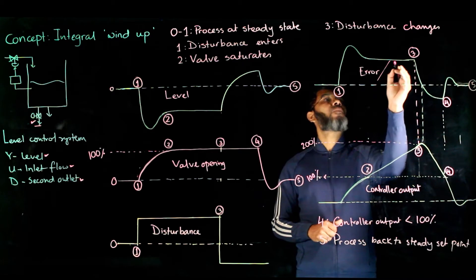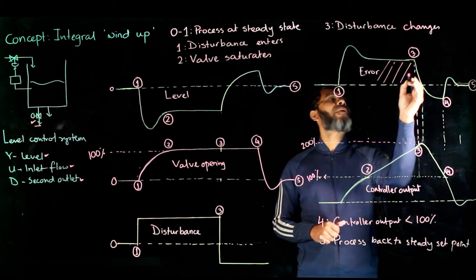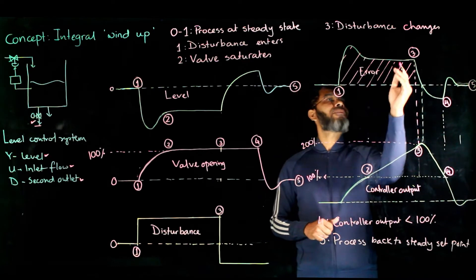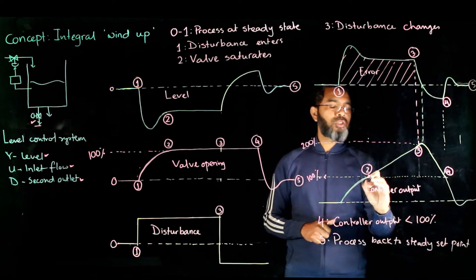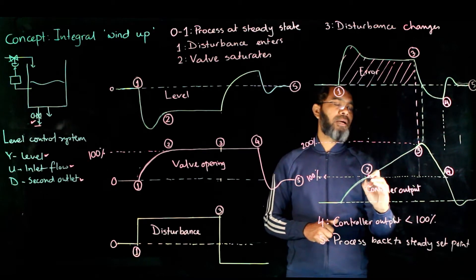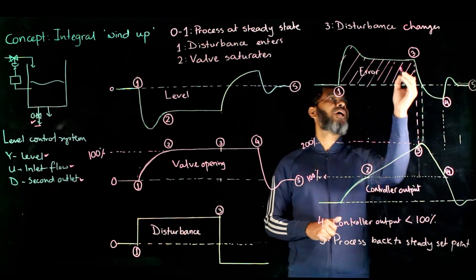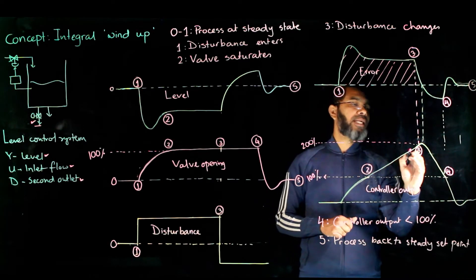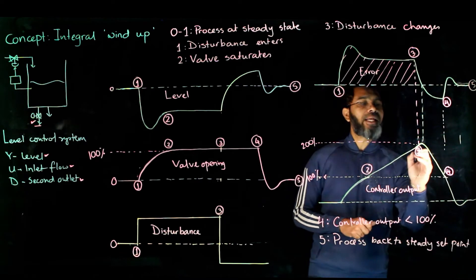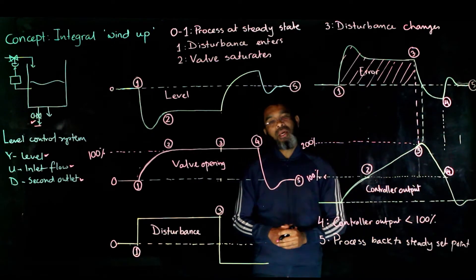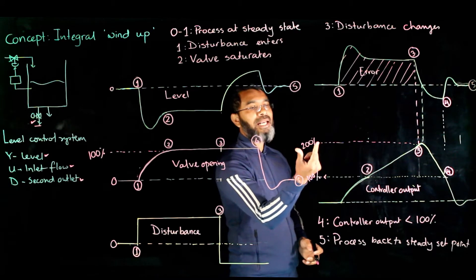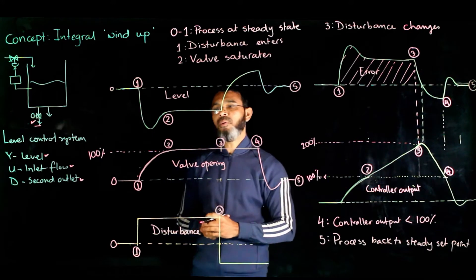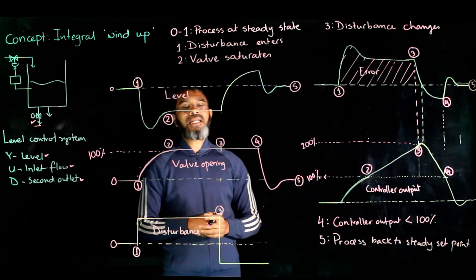The integral action in the controller computes output as the area under the error curve, and this area keeps increasing because of the persistent error. The control action is being calculated beyond 100% and keeps increasing — due to the integral action it rises continuously, reaching say 200%. This is not practically realizable, but the controller output remains at that theoretical value while the valve is still saturated at 100% open.